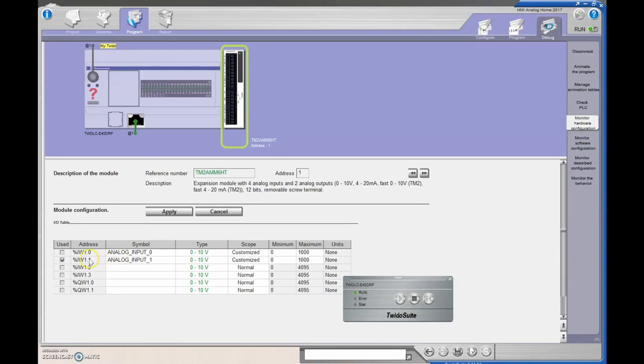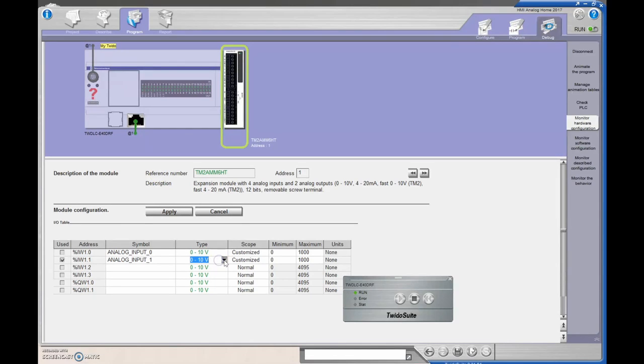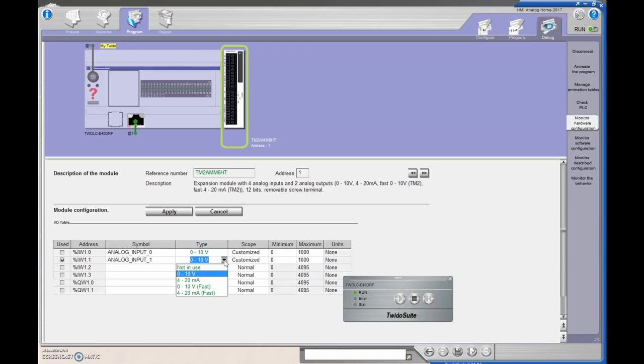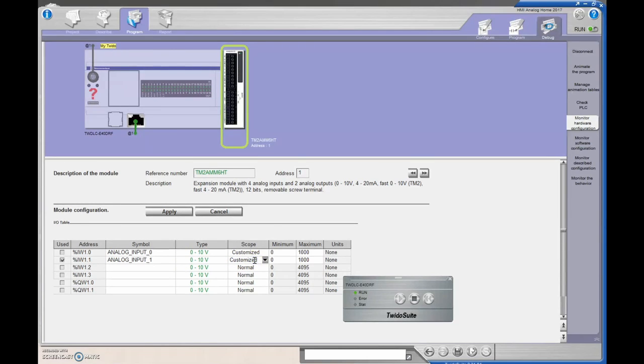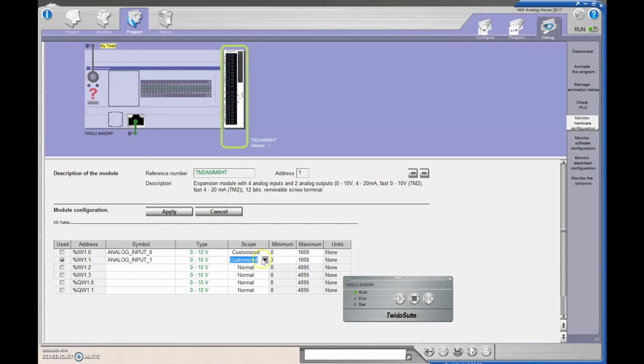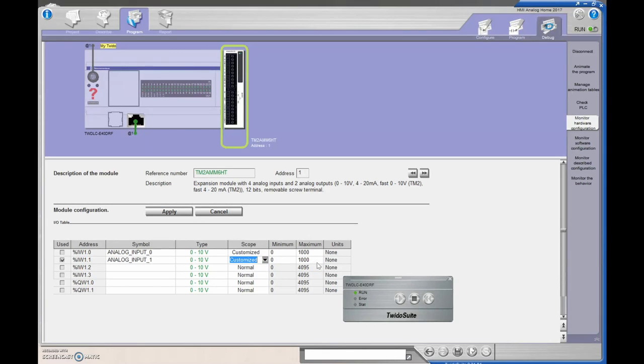So I'm looking at this input right here, %IW1.1, so I'm looking at an entire word. I've gone to 0 to 10 volts, this guy is able to do 0 to 10 volts or a 4 to 20 milliamp signal, so I'm going to use the 0 to 10 volts first. I went with a customized range, so you can go with your normal range or your customized range, so I went with a range from 0 to 1000, 0 being 0 volts and 1000 being 10 volts. Then I could get a number of different gradations in there between my 0 to 10 signal.